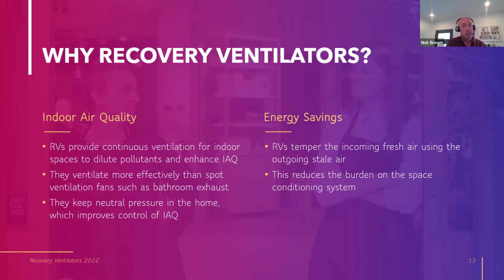They ventilate much more effectively than spot ventilation, such as a bathroom exhaust fan, which is the most common technique for accomplishing continuous mechanical ventilation in the state. They also keep balanced or neutral pressure instead of negative or positive pressure, which improves control at the moisture barrier, the air barrier, generally a little bit more comfortable to be in too. Then there's the energy savings arguments. As was said in chat, I like to use this term, they temper the incoming fresh air using the outgoing stale air. And this reduces the burden on the space conditioning system in winter and summer.